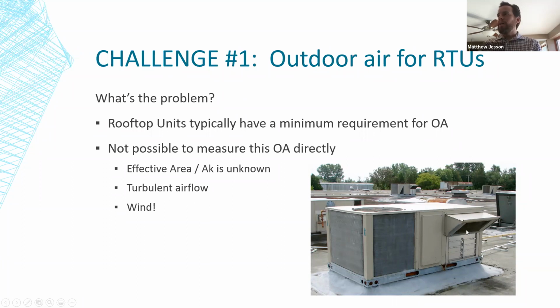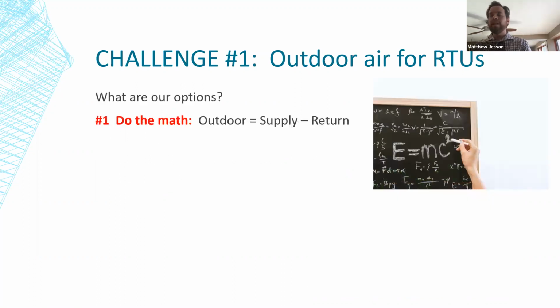Also, your airflow right here is going to be quite turbulent. If you think about it, most of the time, the outdoor air control damper is going to be right behind this. And when you're at minimum outdoor air, it's going to be throttled back quite a ways, and so that's going to create more turbulence. And finally, you're outside. Wind is a factor. Any little bit of wind can really skew a reading that you're trying to take. So measuring that directly just isn't an option.